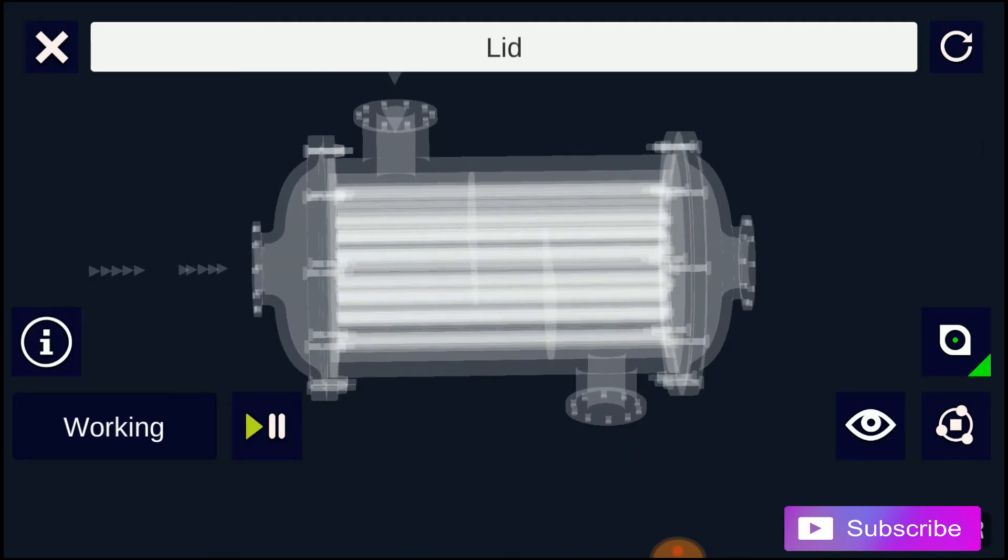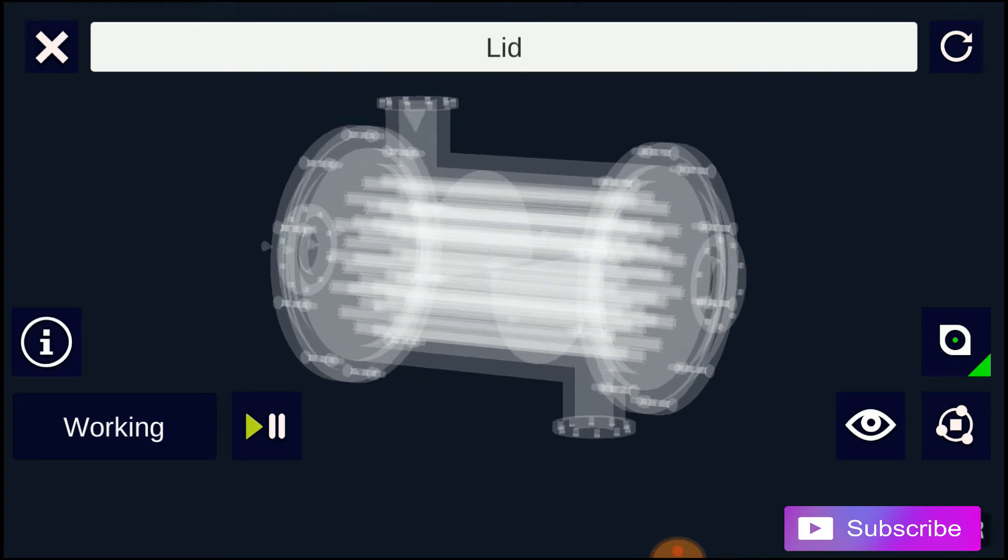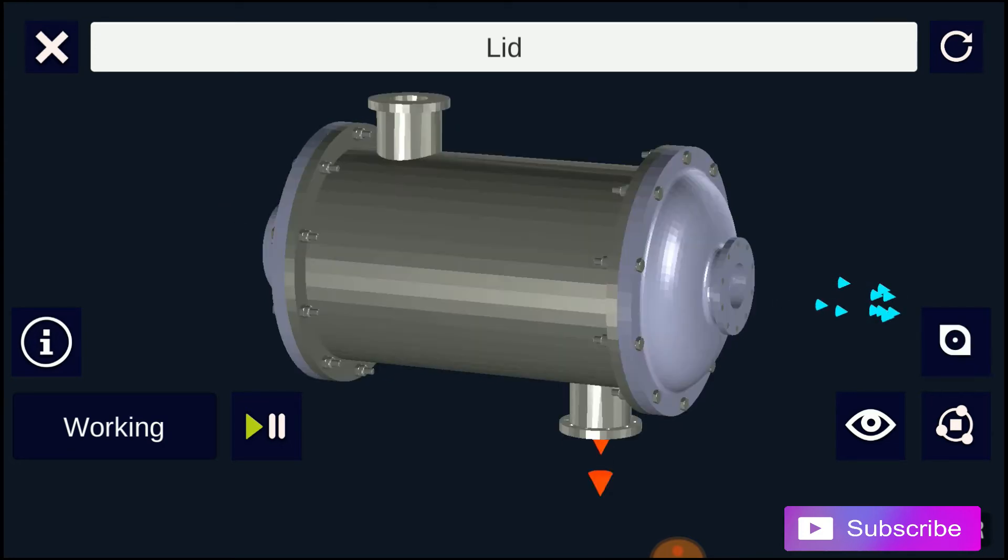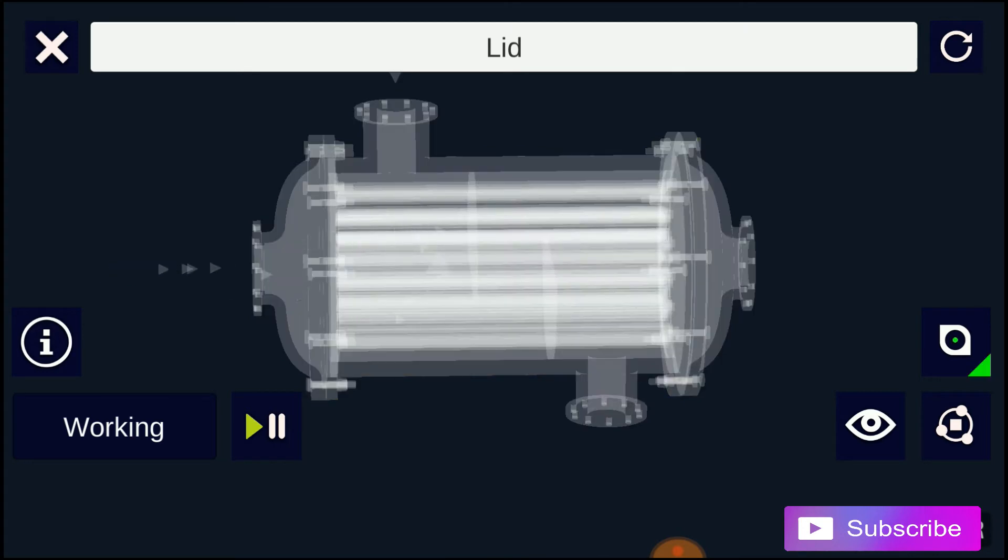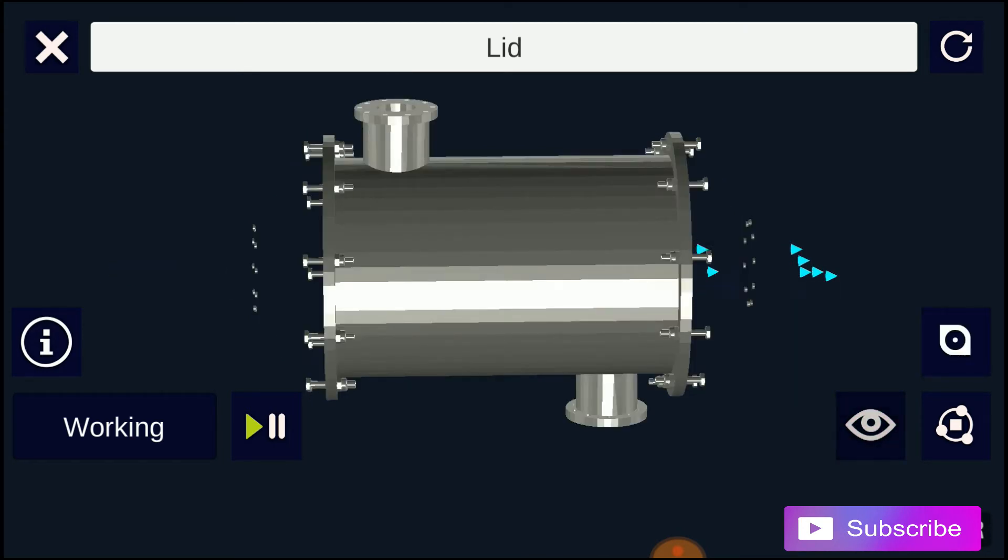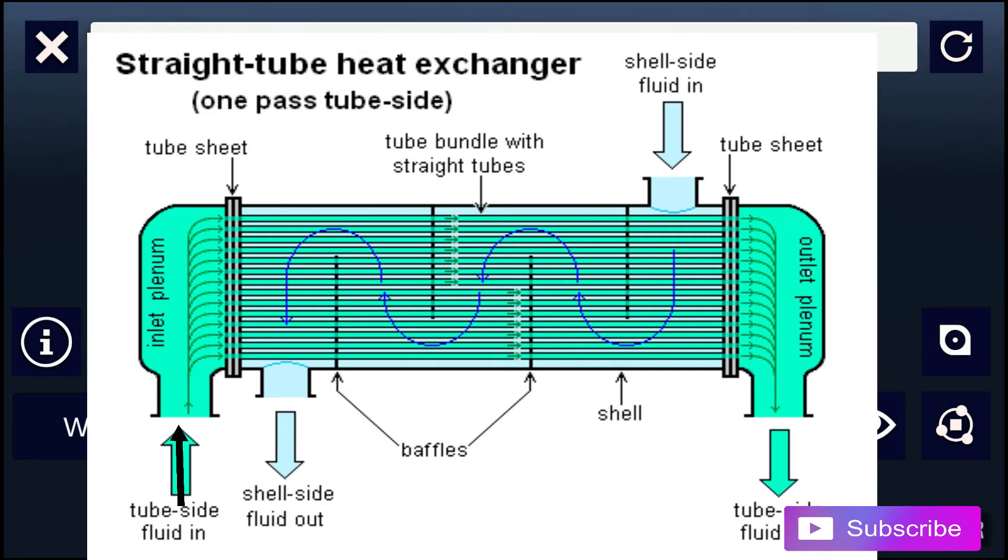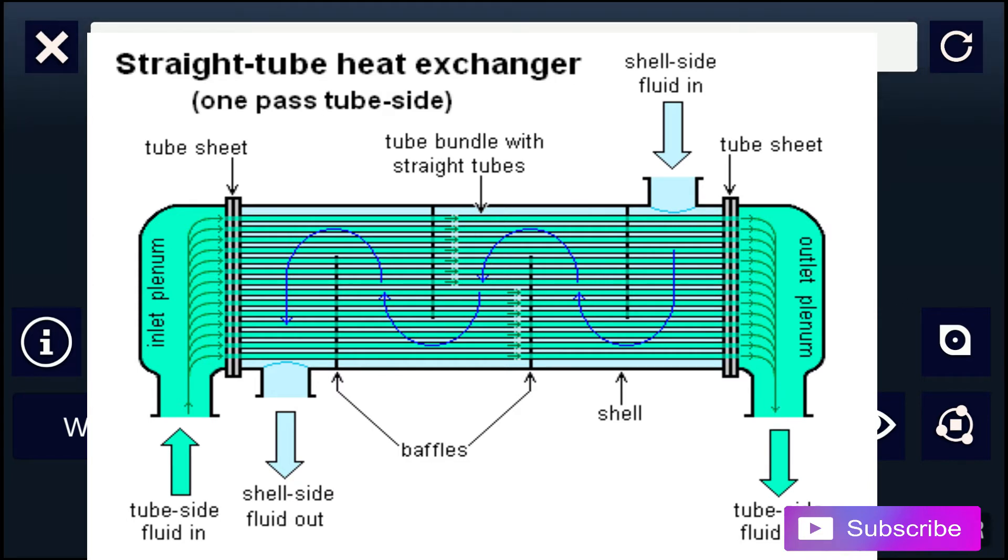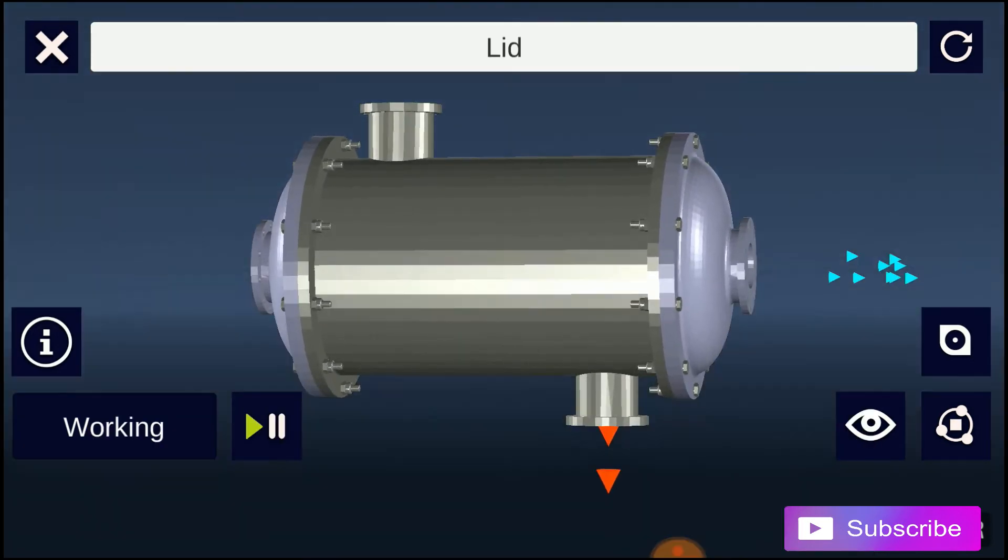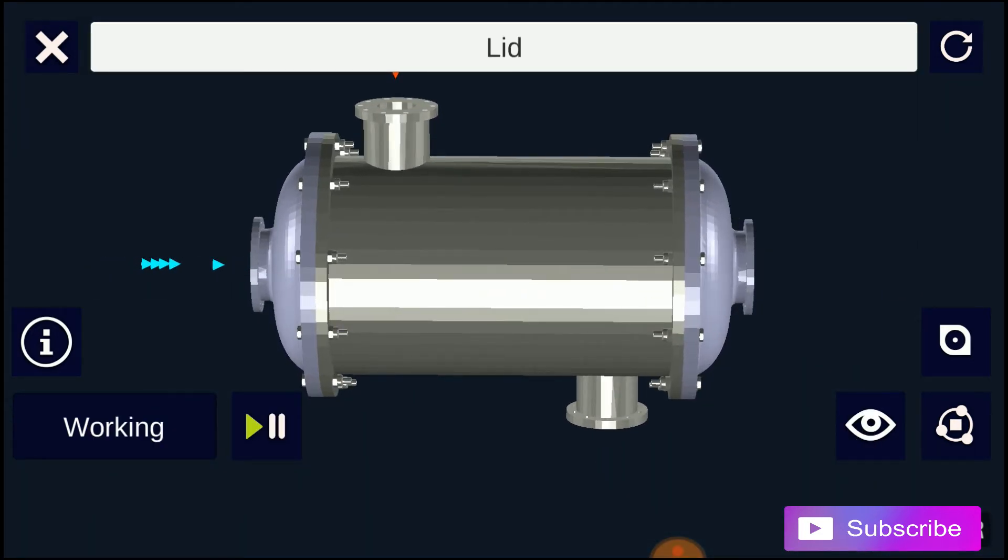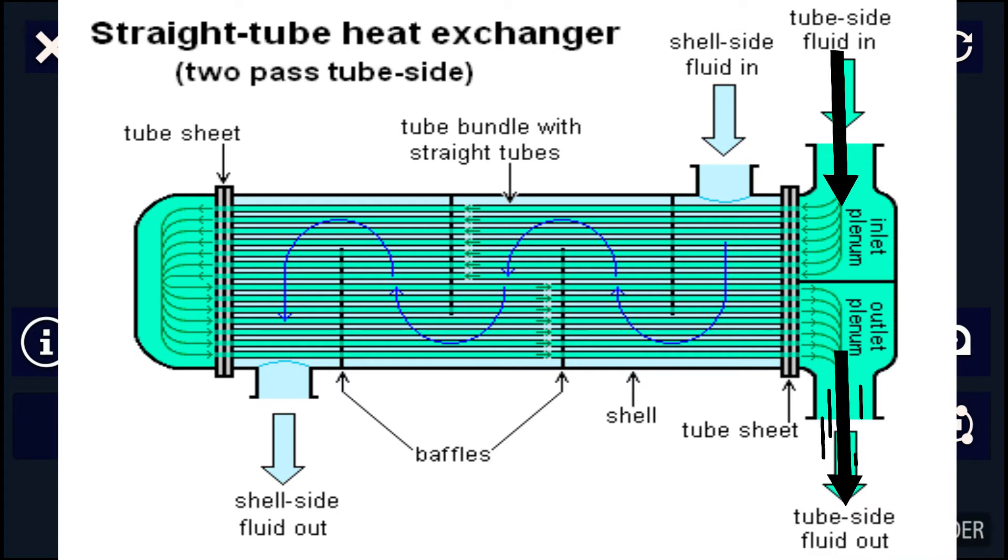Most shell and tube heat exchangers are either one, two, or four-pass designs on the tube side. This refers to the number of times the fluid in the tubes passes through the fluid in the shell. In a single-pass heat exchanger, the fluid goes in one end of each tube and out the other. Surface condensers in power plants are often one-pass straight tube heat exchangers. Two- and four-pass designs are common because the fluid can enter and exit on the same side. This makes the construction much simpler.